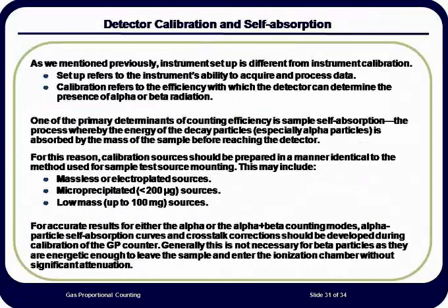Self-absorption curves are prepared by taking solutions of varying solids content. The solids should be of the same salt and have the same known amount of radioactivity added to each solution. The range of solids usually varies from about 5 milligrams to approximately 120 milligrams for alpha and up to 200 milligrams for beta.